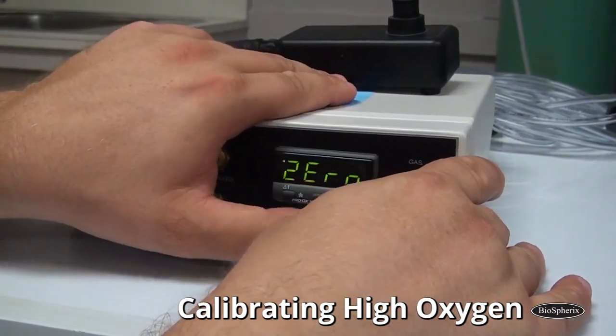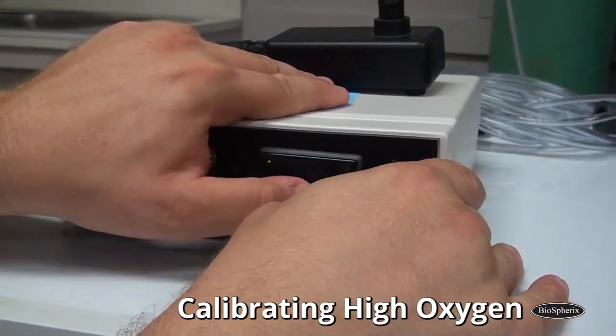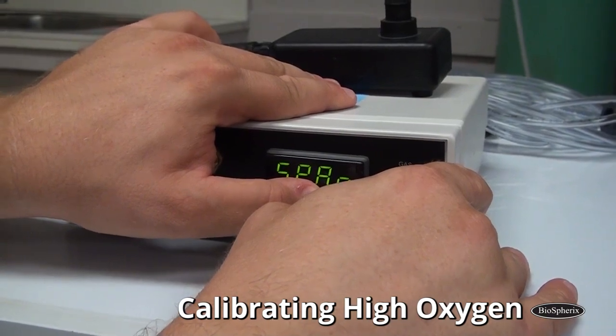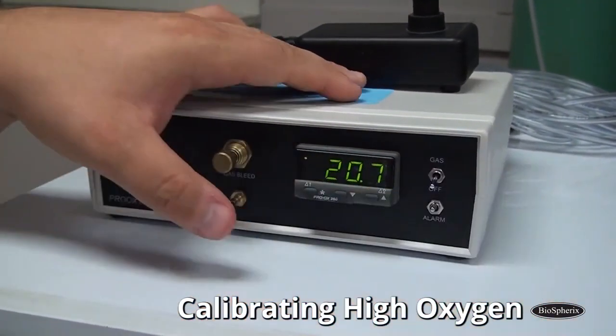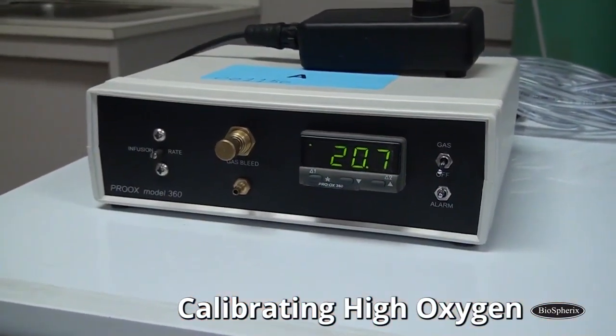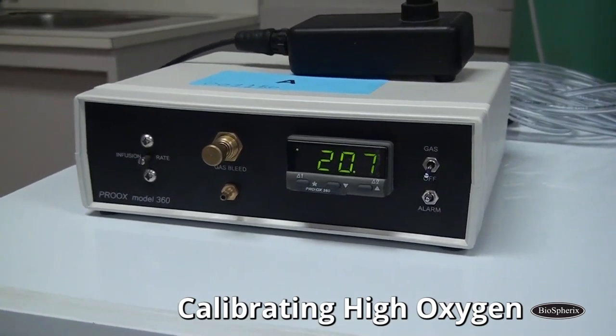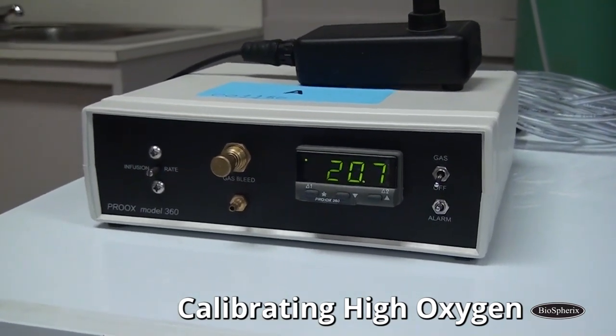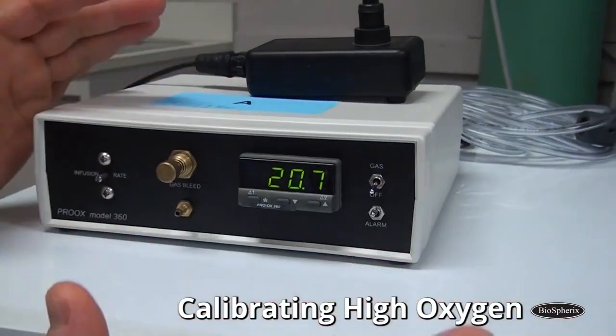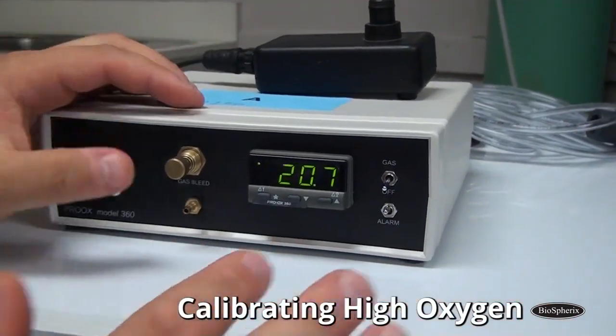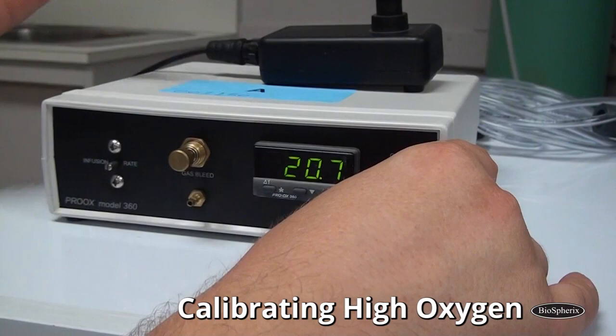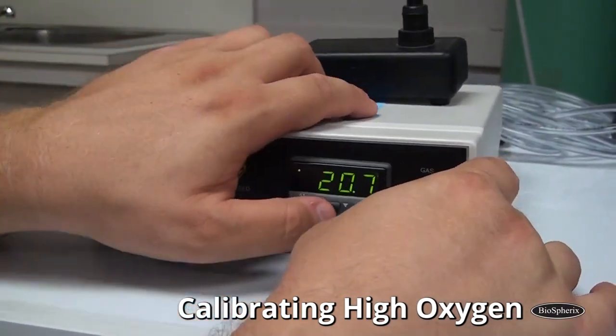And now I need to save that. Exit the program mode. So I hold up and down for 3 seconds. And then the reading comes back. And it's actually a little lower than what I want to be. I can get more accurate. The 0 you can get real accurate. So I'm going to just, and this is typical, I'm just going to do it again.